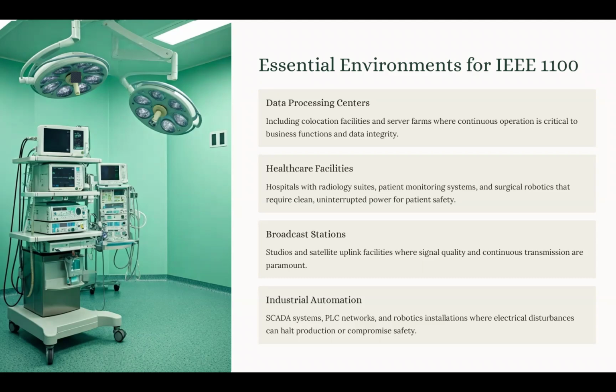It covers SCADA or PLC networks and robotic installation control that control entire production lines, and any disturbance can lead basically to production downtime or safety hazards. For those environments, IEEE recommends some practices like load segregation and zone design. Another practice is grounding and signal integrity, and another practice is surge and harmonic control. Now, if we don't use those practices, in industrial automation, it would mean unexpected production shutdowns, robotic malfunction, or even hazardous conditions due to logic errors in PLC or communication ports.